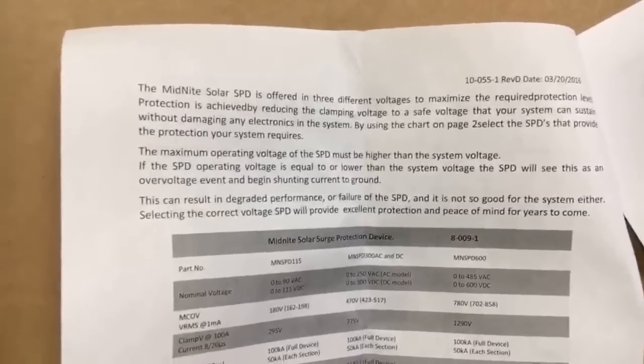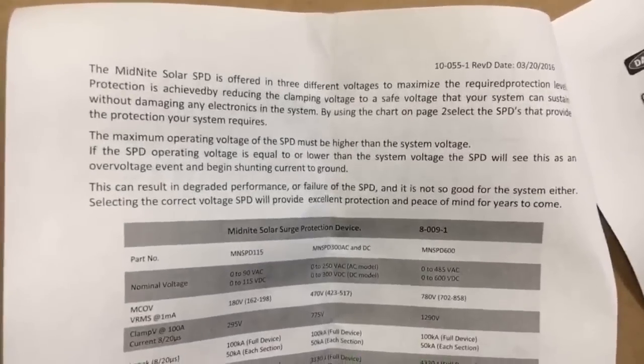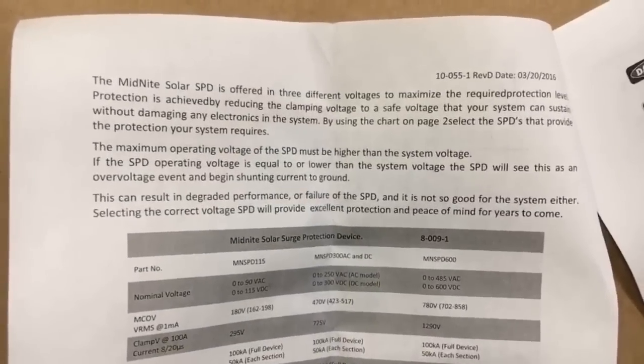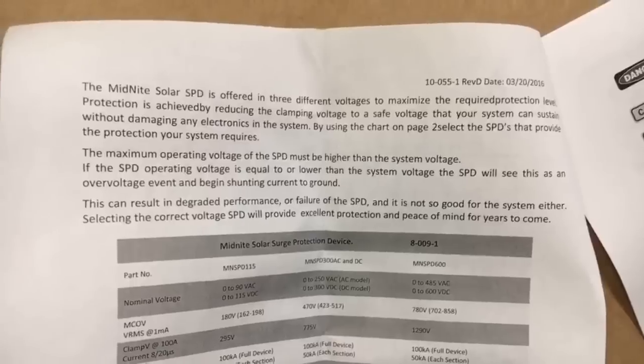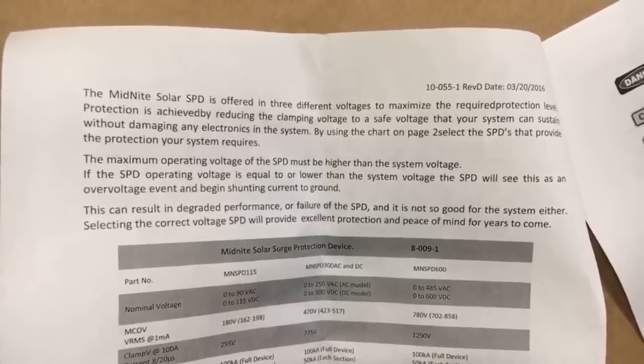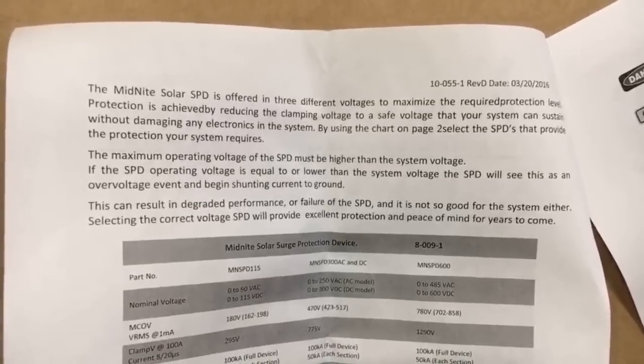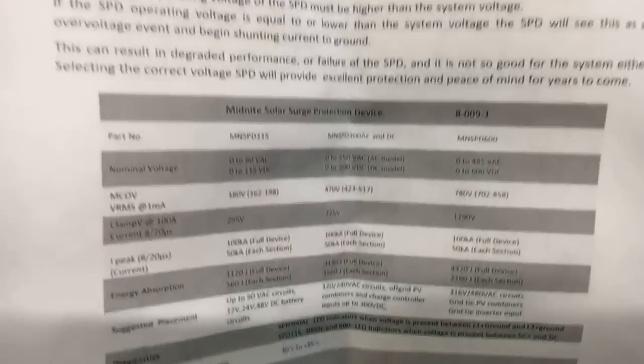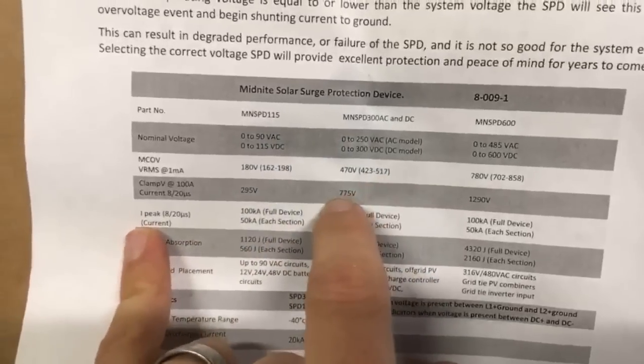It says the maximum operating voltage of the SPD must be higher than the system voltage. If the SPD operating voltage is equal to or lower than the system voltage, the SPD will see this as an overvoltage event and begin shunting current to ground. So it shows you when it starts.